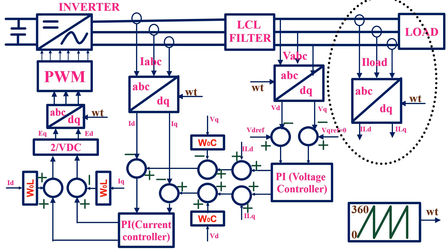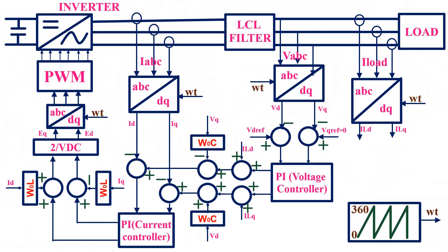One major change is that now I am sensing the load current and transforming it into D and Q axis currents. Another change is that I have modified the voltage controller block — I am now taking into consideration the load current values and the filter capacitor values. Here omega-zero is the grid frequency and C is the filter capacitor value.